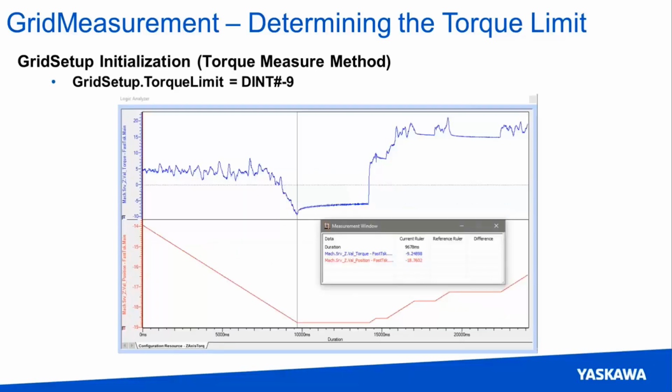Another example, this one nicely shows the torque getting restored back up to 20, or the range of 15 to 20, but the torque graph here clearly shows that it decreased significantly, and at which point the position was not changing because it didn't have enough torque to push any further into the bed. So we took the measurement and proceeded on to the next measurement location.